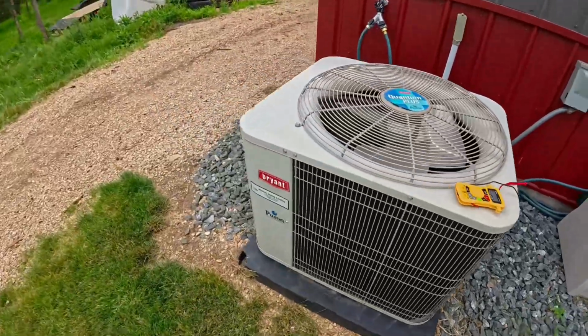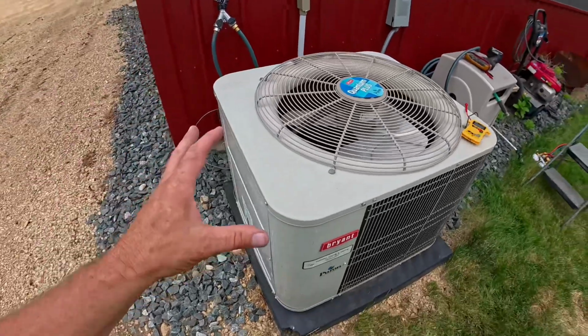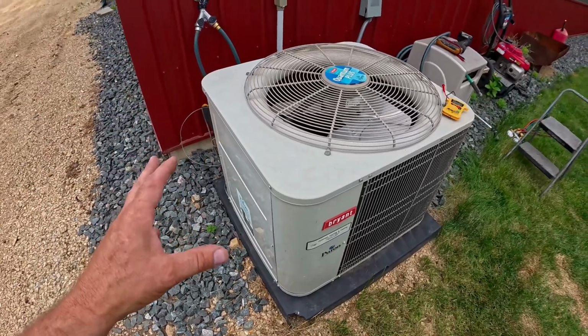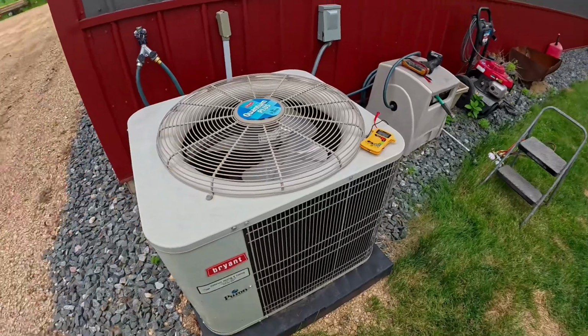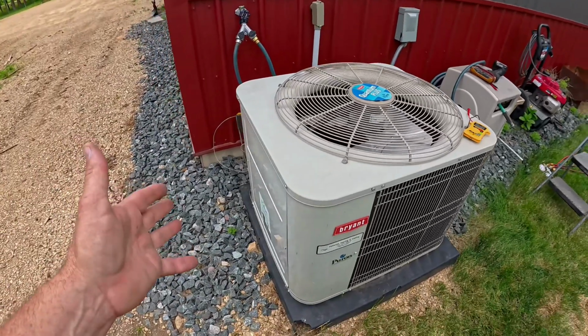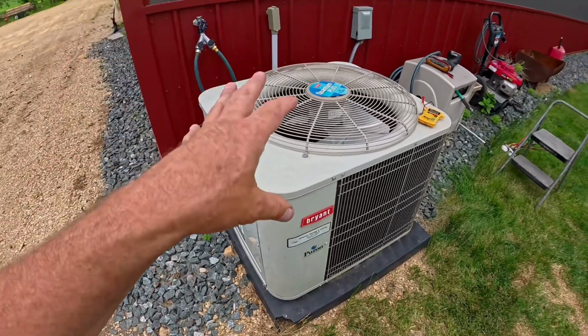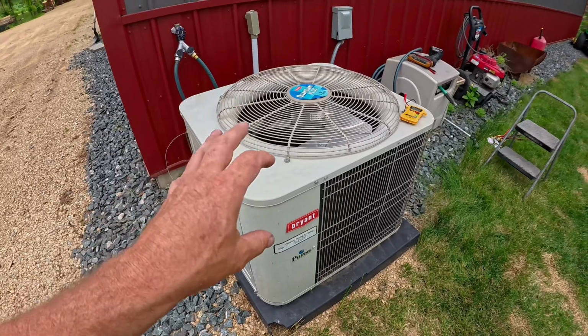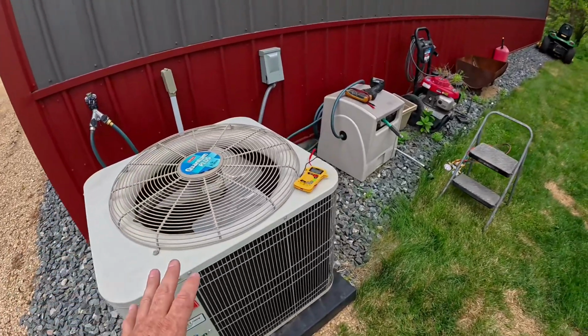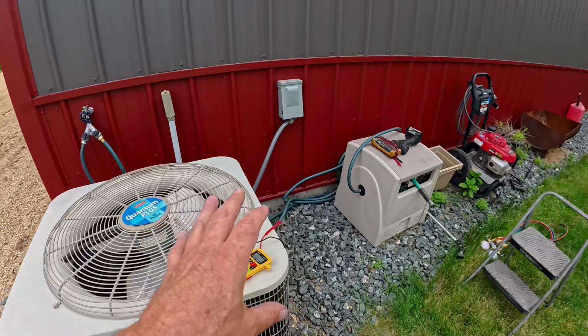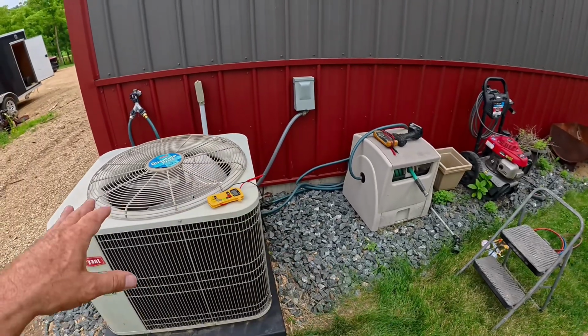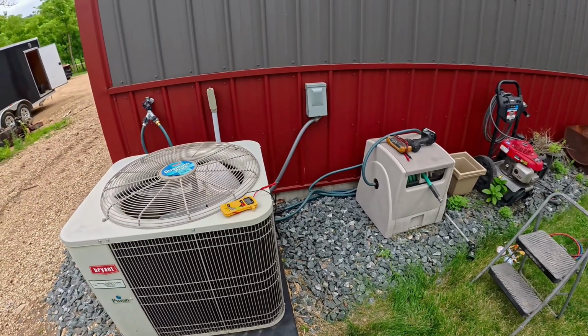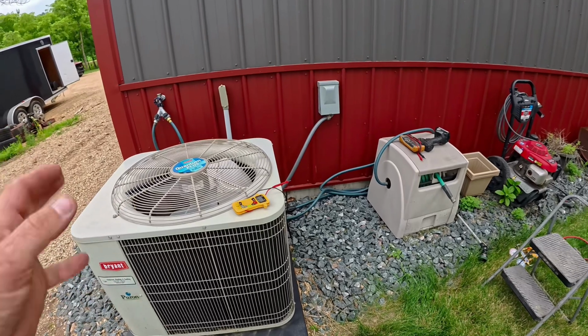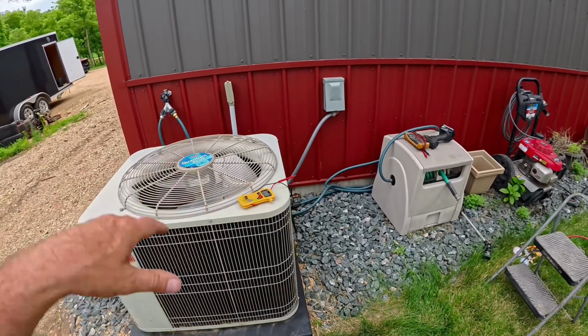Now if you come out to the unit and you hear a slight buzzing coming from inside the unit, very low buzzing, but nothing is turning on, that's telling me that the contactor is in fact closed and it's calling for the cooling to be running. So the problem is usually the high voltage, which is 220 volts. And if you're not comfortable with high voltage or electricity, stop right here, call a technician, and let them handle it. But if you're comfortable dealing with electricity, well, then we're going to dig a little deeper.